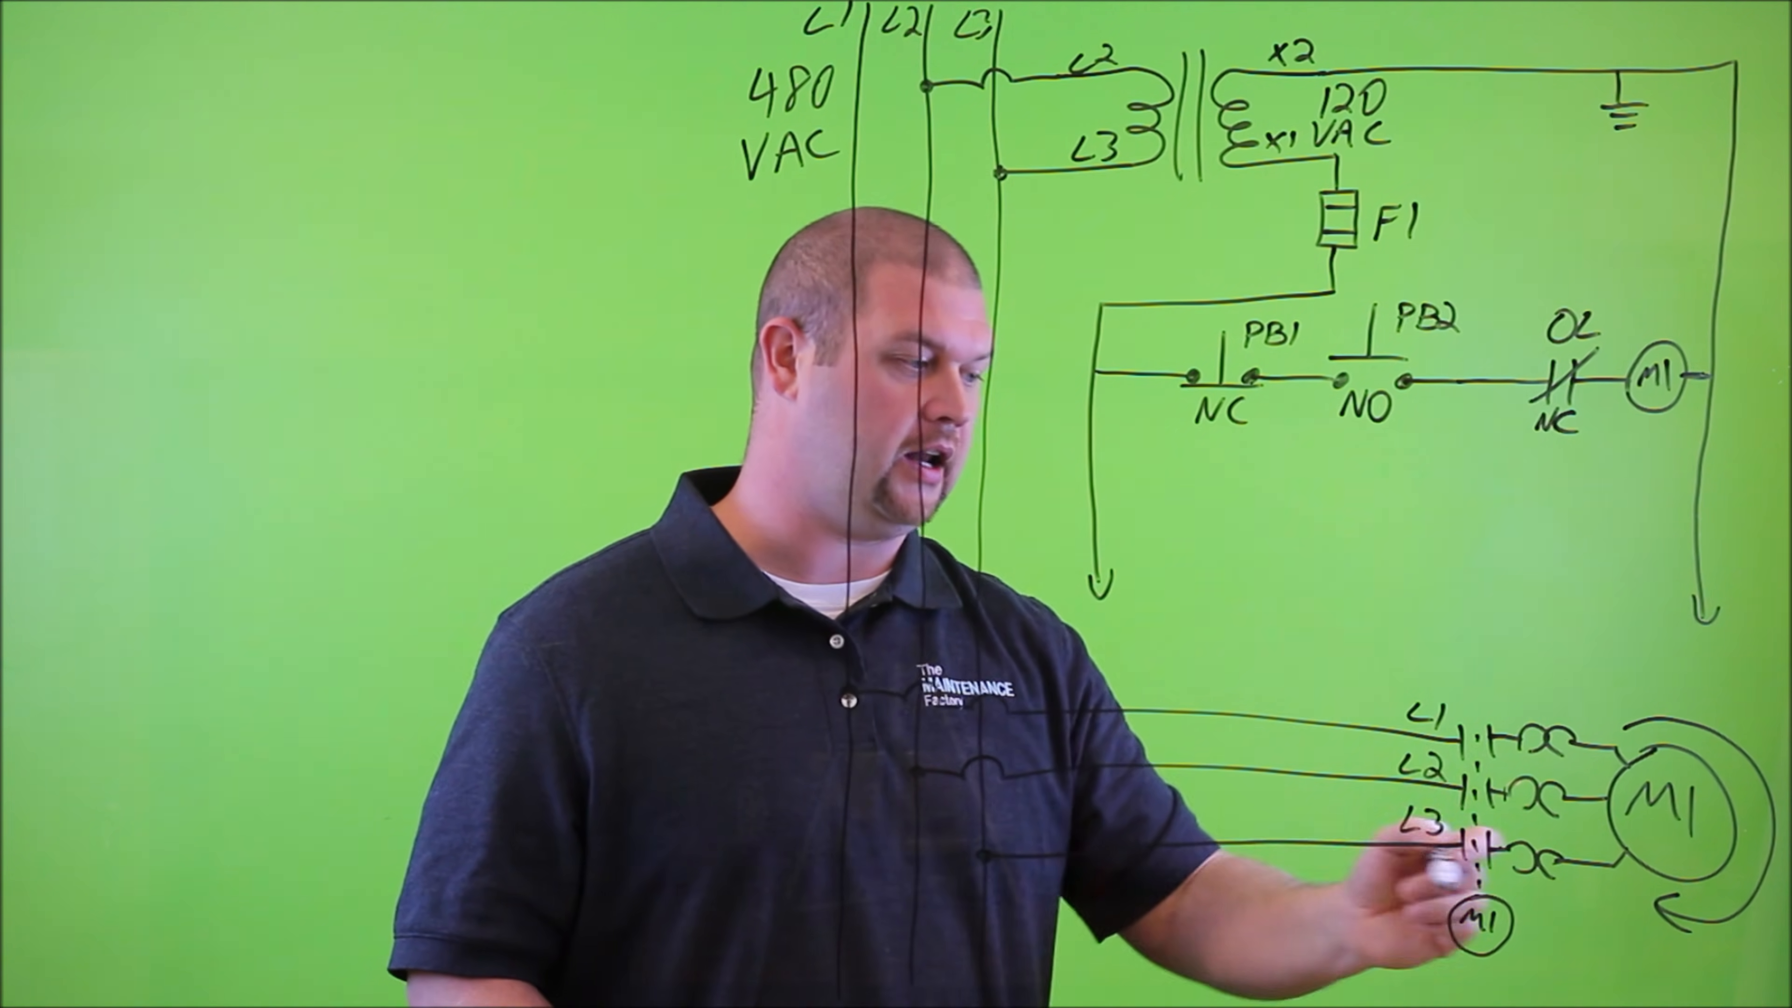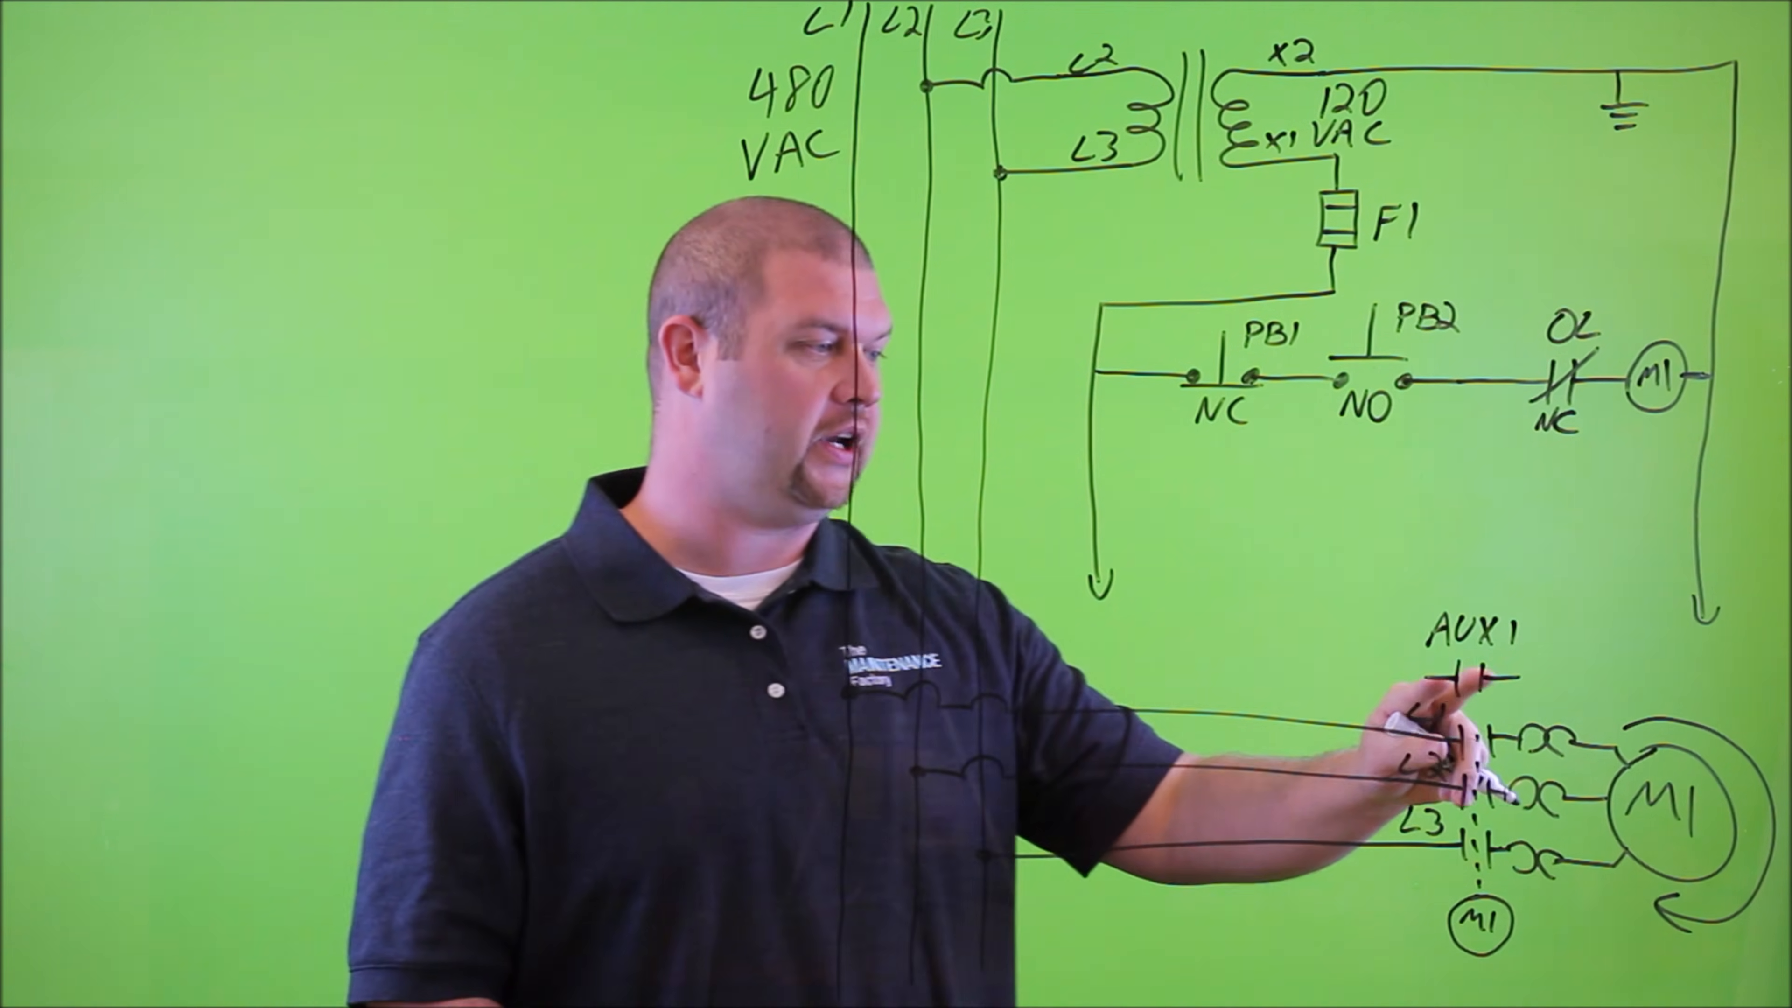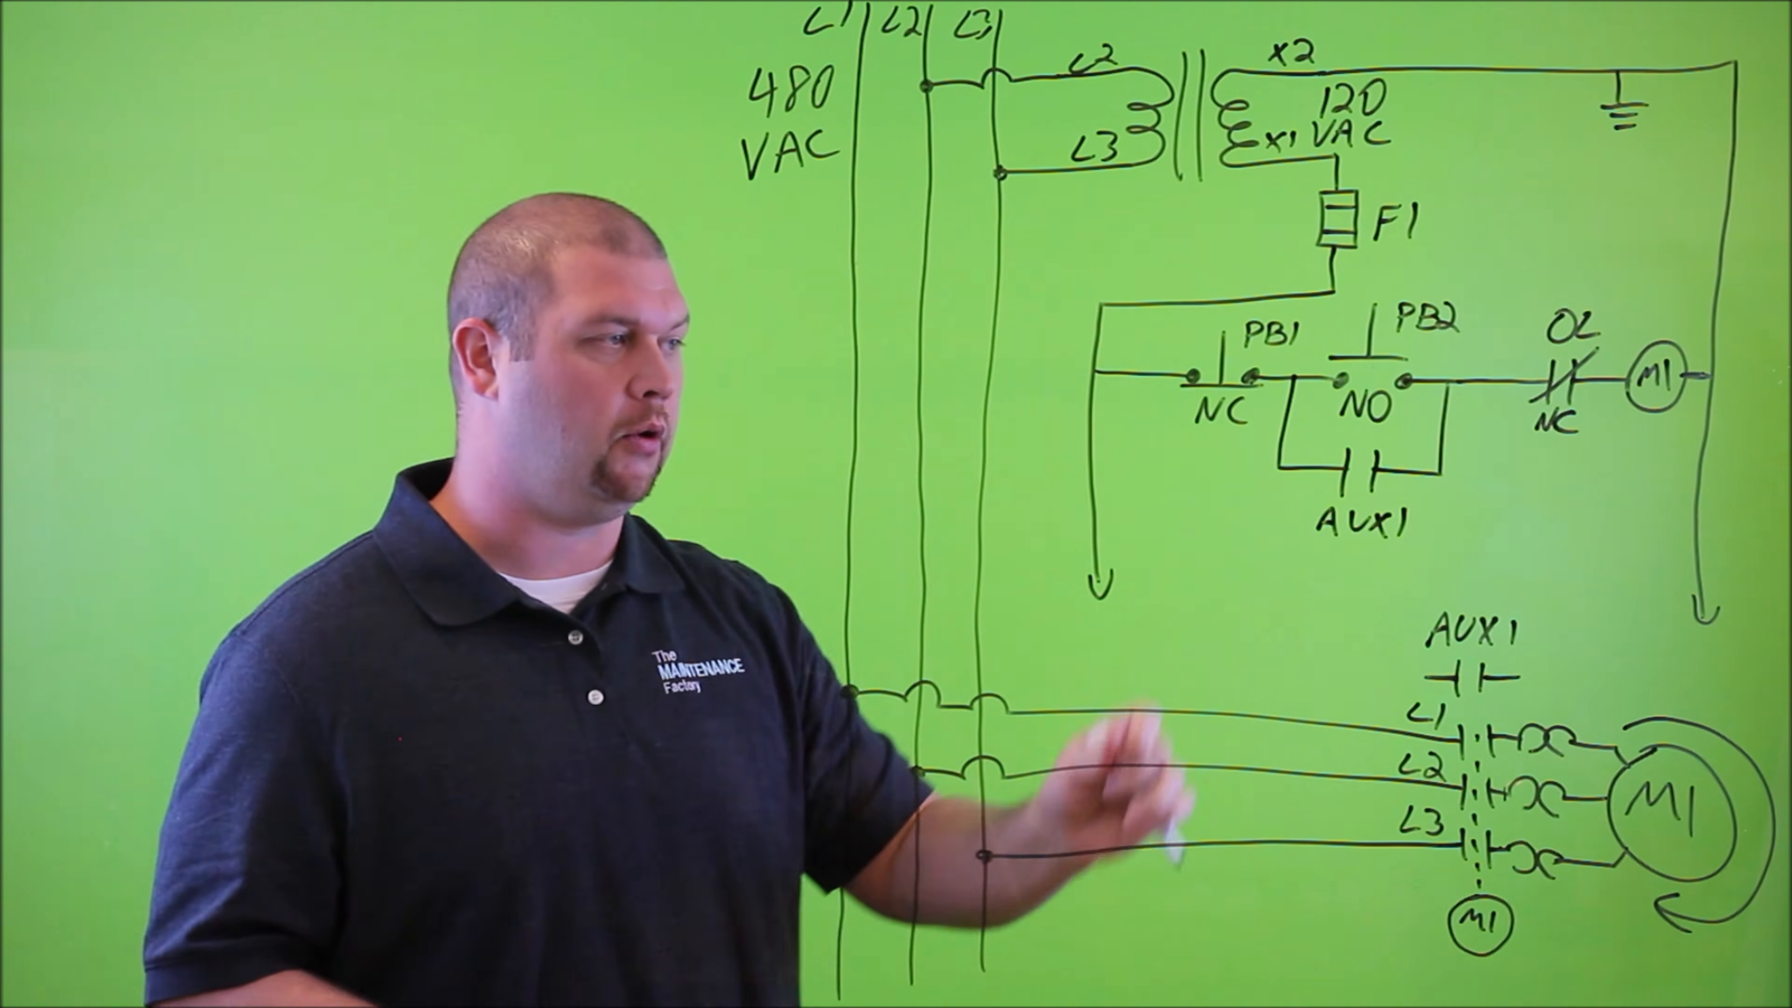And where we're going to get that at is from this contactor. This contactor off to the side will have another normally open auxiliary contact, and we're going to call it AUX1. Now, what we need to do is draw this auxiliary contact in parallel with the start button. So let's put it right here. And we'll label it AUX1.